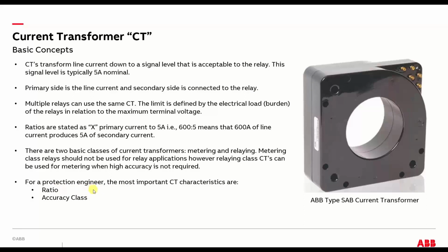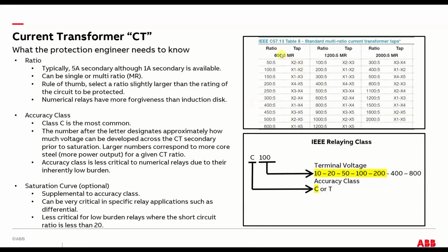But from a protection engineer standpoint, the most important things to know about the CT are the ratio and the accuracy class. I'll try to go through some of this quickly. Here's a table of some standard CT ratios. These are for multi-tap CTs, so you can get a CT that you can reconfigure its ratio based on what taps and jumpers you put on it. So you can get a 600 to 5 MR, which would be multi-ratio, and that can be set to drive either a 50 amp load or a 600 amp load, and all these variations in between.